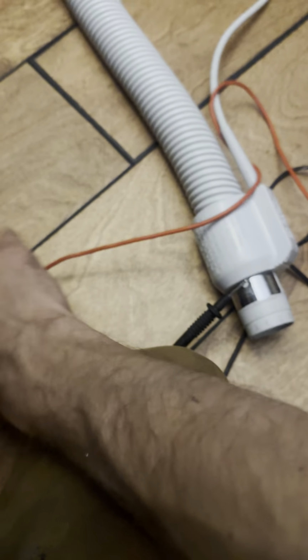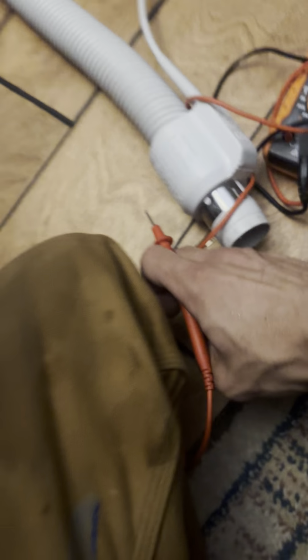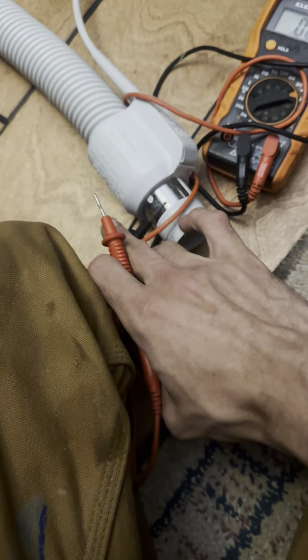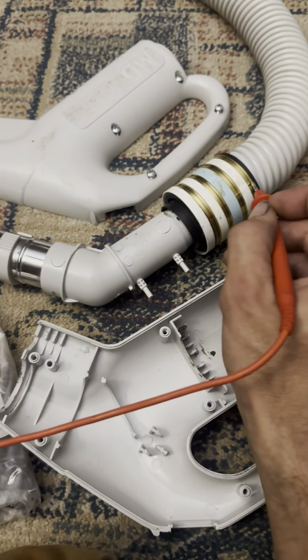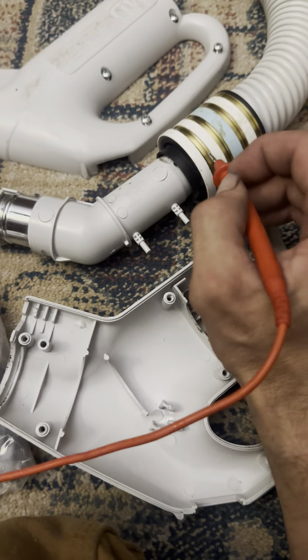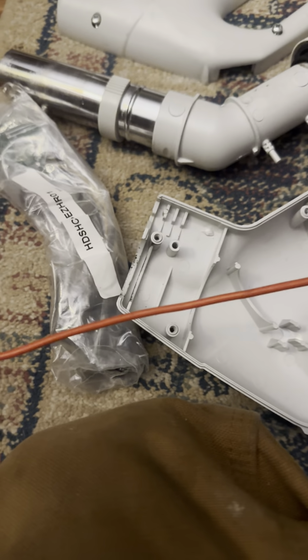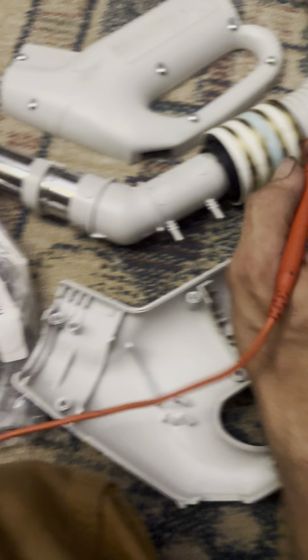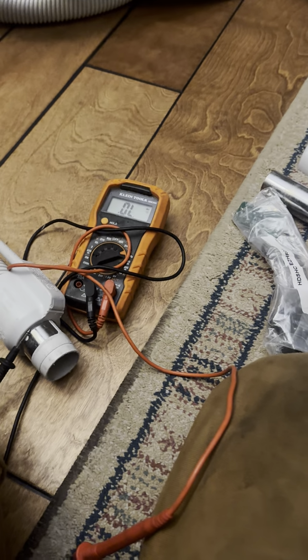Now, flip it over to the other side and test the ring on this side. The low voltage tends to be on the bottom rings. Uh-oh, that's because of touching the plastic. Make sure you're touching the metal surface. I'm trying to do this one-handed. I've been doing this for years, so, see, oh, I was wrong. Uh-oh. See, we got continuity. So we know our low voltage side of our system is actually working.